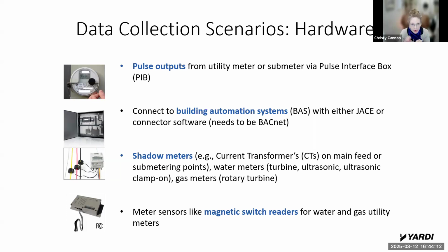It has little wires, so we can connect a transceiver to it and then get that read data to a central data collector. We interface with building automation systems, especially our larger commercial clients, like think huge 2 million square foot malls, that type of thing. They will frequently have their tenant submeters tie into the building automation system because that makes it easier to compile data to bill them back their allocated utility cost.